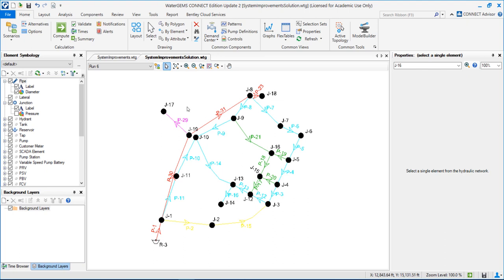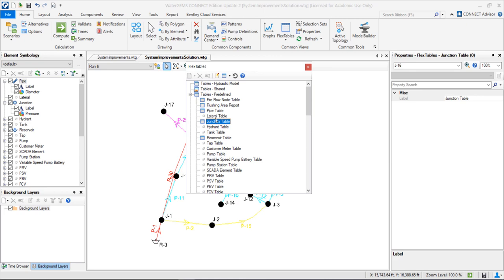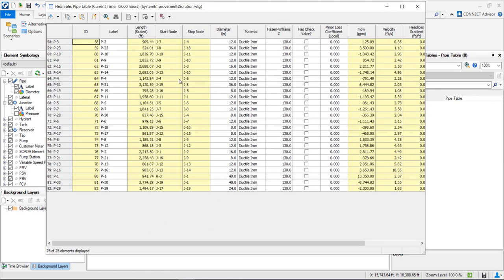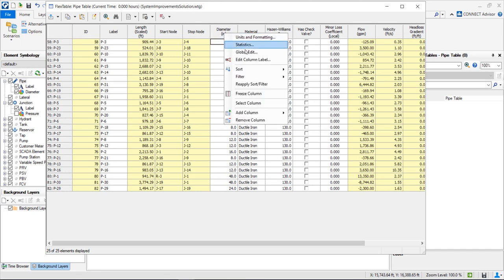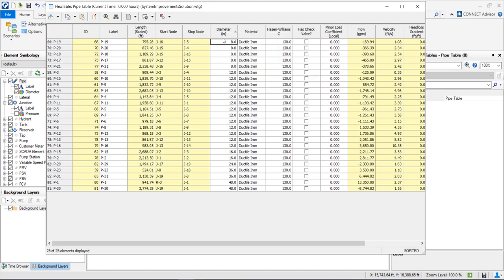Now we can see the pipe diameters proposed for run number 6. We can go to the pipe table and see the proposed diameters: 8 inch, 12 inch, and 6 inch for the smaller pipes. The 24, 36, and 48 inch are the bigger transmission main pipes.